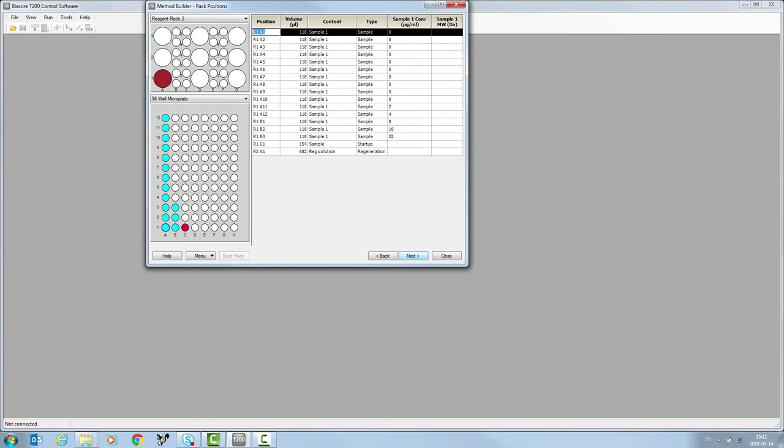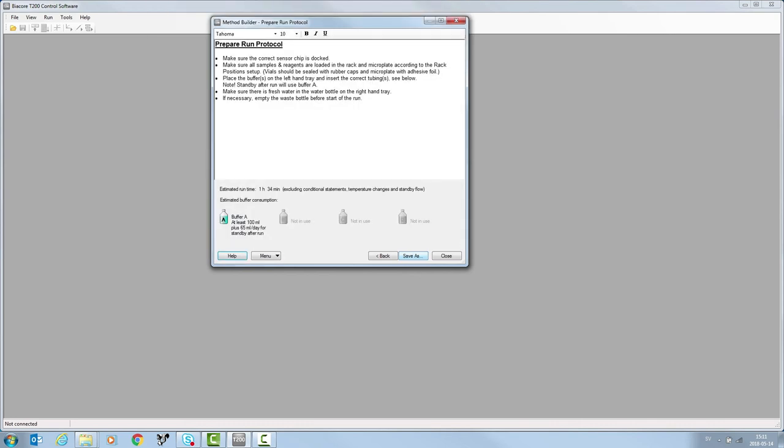Click next. The prepare run protocol is displayed, a checklist to ensure the system is ready to start your run. Estimated runtime and estimated buffer consumption are also displayed.